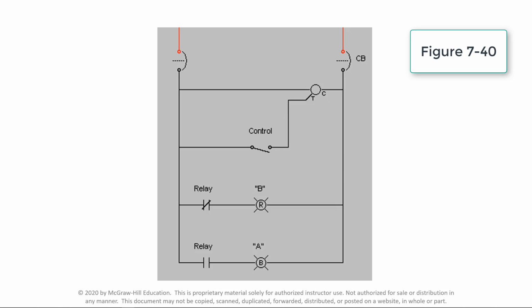Loss of input voltage resets the unit. Load A becomes the lead load for the next operation. An option feature found on these relays allows an operator to terminate alternating operation and cause only the selected load to operate. This feature allows users to select one of the two loads or alternate between the two.